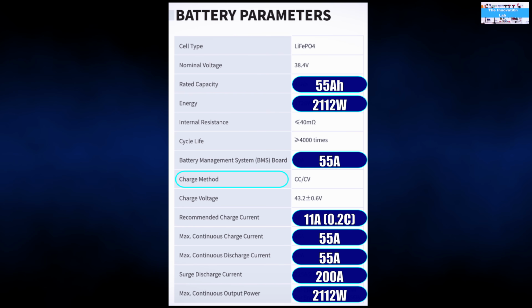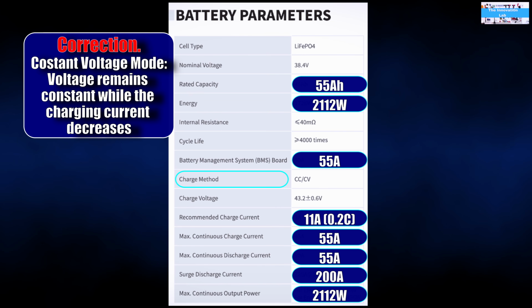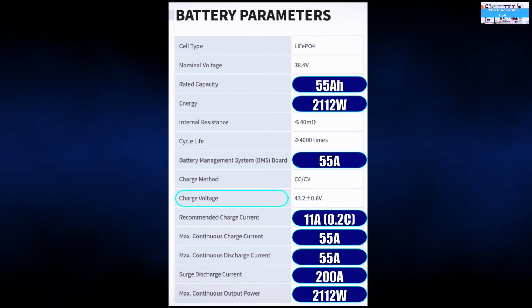In the constant current charge mode, the current stays constant while the voltage rises slowly. In constant voltage mode, the reverse is the case. The battery supports both. It has a nominal charge voltage of 43.2 plus or minus 0.6 volts, and a recommended charge current of 11 amps, which translates to about 0.2 C.